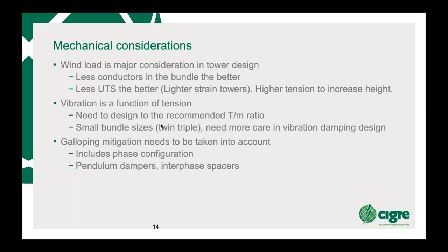Now galloping is something which comes into play where you have ice on conductors. It forms an aerofoil and then causes the conductor to move in a very large arc, which can actually destroy a tower in a couple of days. So this is very serious. And the phase configuration is quite important so that you don't have phases one above the other in a double circuit line. That's why you'll see some lines where the center phase is actually further out than the top phase and bottom phase. That's due to galloping mitigation.